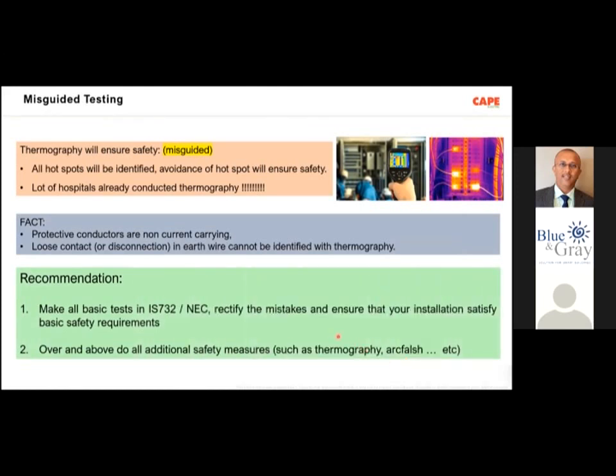The recommendation is you should do all the basic tests as per IS 732. Say, for example, imagine you have completed the wiring in your building and the wires are inside the conduit. After making the continuity resistance test, if there is a loose contact, you will come to know. So you don't need thermography. The basic recommended test is the continuity resistance test, and it will reveal a loose contact.